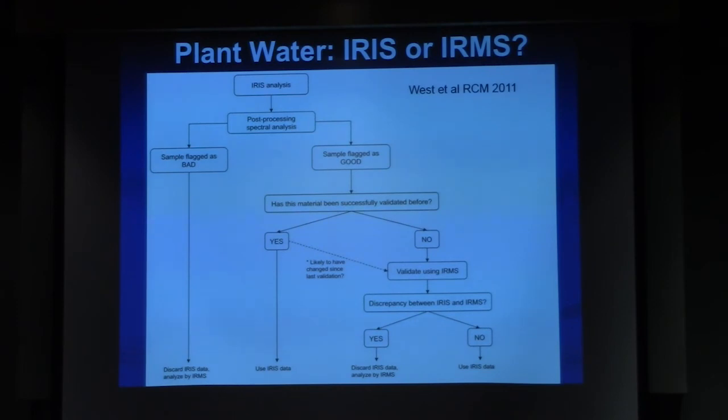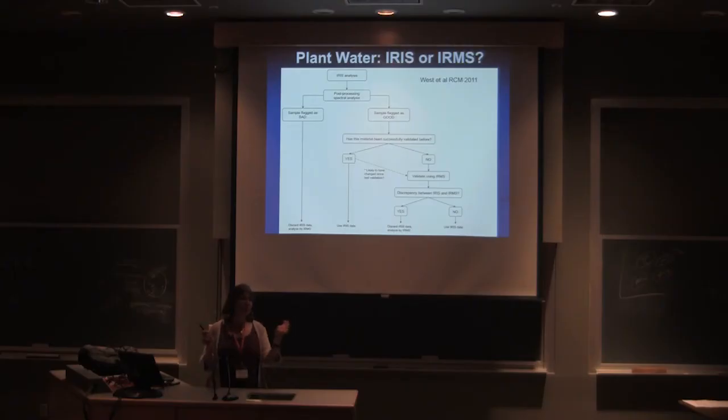So alcohols get absorbed as well. Again, this one is not measuring mass, it's measuring absorption of the light that's shown through there. And so anything that absorbs is going to cause a perturbance in their calculations of what the isotopic ratios are going to be. They're aware, they can flag it for you in some cases, but in other cases it may not be enough. And so you have to decide if you're going to be able to trust the laser or not, and there's some steps you can go through on these ones.